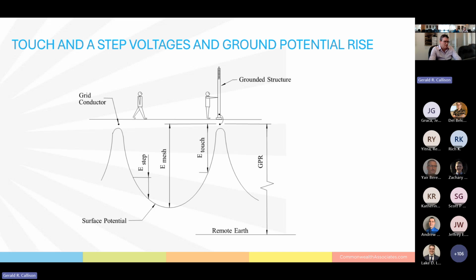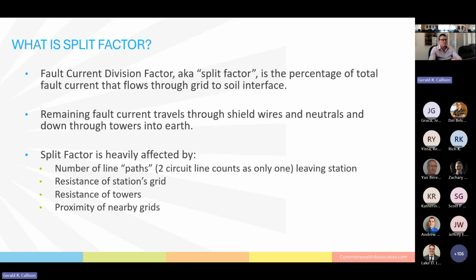So another thing that I've tossed around a lot, and it's going to be very important to what Rich is going to talk about, is split factor. Fault current division factor, which is commonly known as split factor, is the percentage of total fault current that flows through the grid to soil interface back to remote earth. Now, all the current has to go somewhere back to remote earth. If it's not going through the grid to soil interface, where on earth is it going?